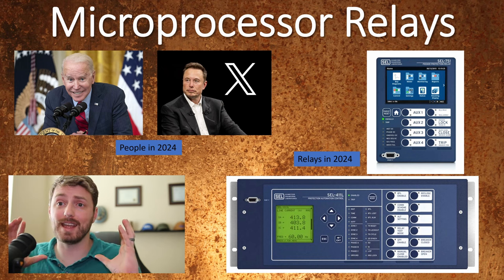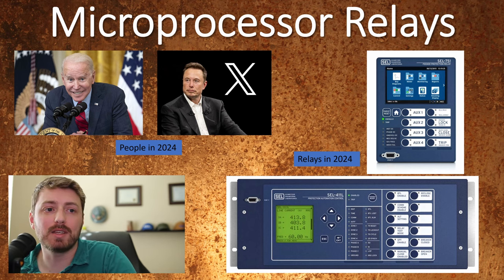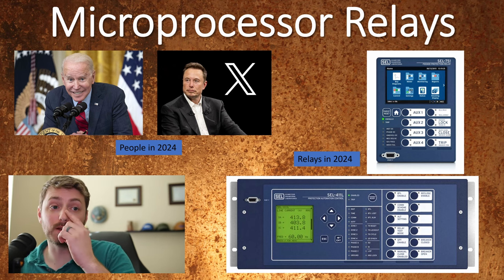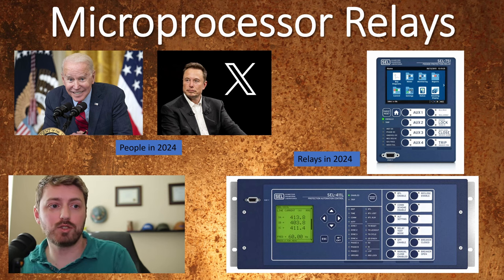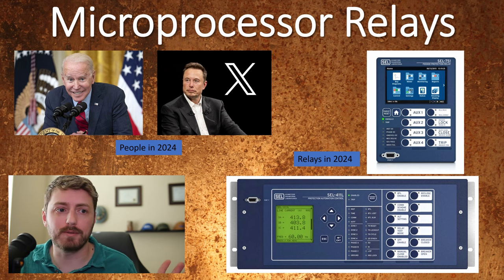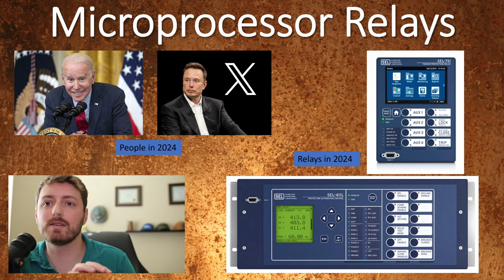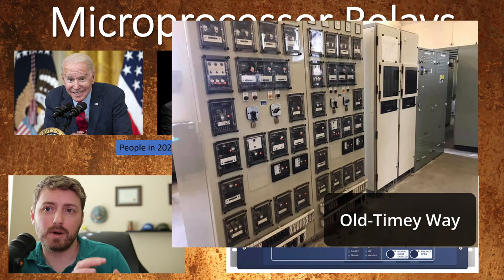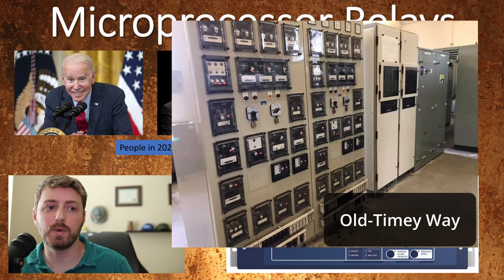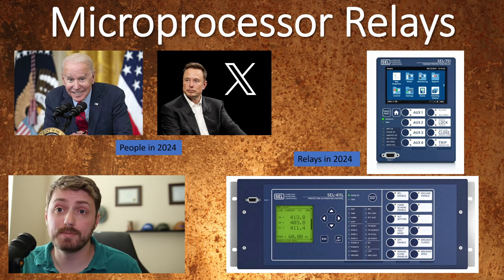That brings us to today and relays that are essentially amped-up PCs designed to protect our grid. The modern microprocessor-based multi-function protection relay is massively powerful. Secure and high-speed communications are baked right into the protection relays, meaning we can get real-time monitoring data straight from the horse's mouth, or get cheeky and use the trip and close functions for automated control of substations and breakers. Due to the massive increase in processing power, we can cram dozens of protection functions into one little box instead of having one protection function per box per phase. For the same level of protection offered by a wall of electromechanical or solid-state relays, we can use a single multi-function relay like the 751 or one of these 411s.